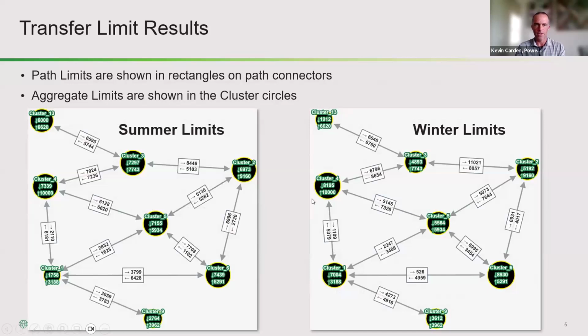Here are the results of the transfer limit analysis. We have the 8 clusters, and we calculated the transfer limits for summer and winter - different limits in the sending and receiving directions. The aggregated constraints are defined for each zone inside these bubbles. This information ultimately helps us identify where we expect to see some binding constraints.